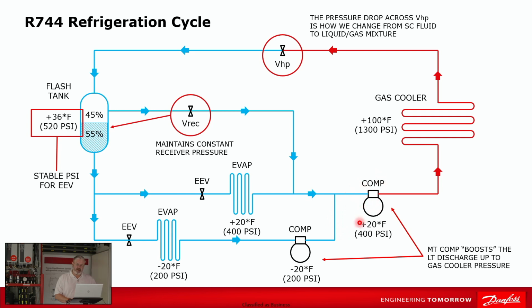And then the medium temp has three connections: the medium temp evaporator return suction, the discharge from the low temp, and the flash gas bypass. And again, if you have questions along the way, please put them in the ask question box. We're going to pause in a few minutes and we can answer them and back up if we need to.